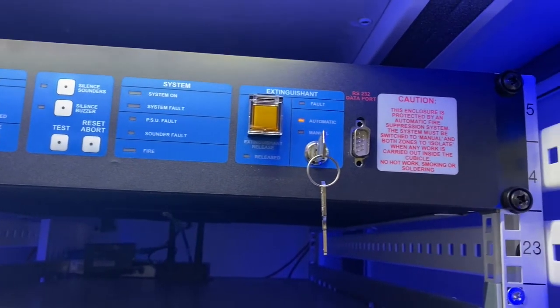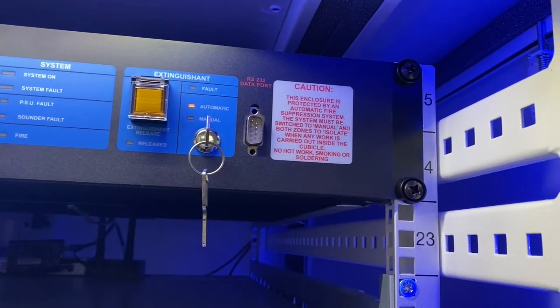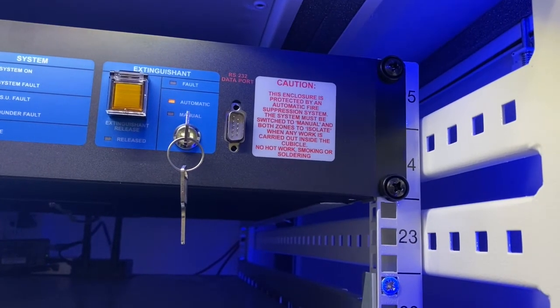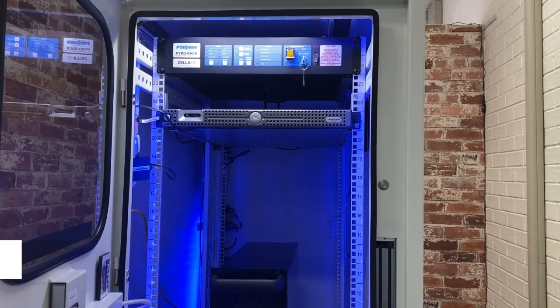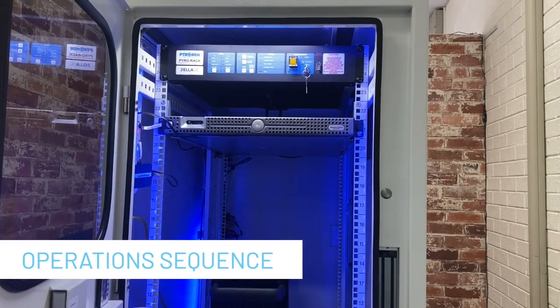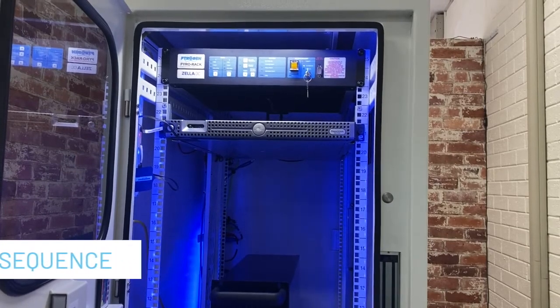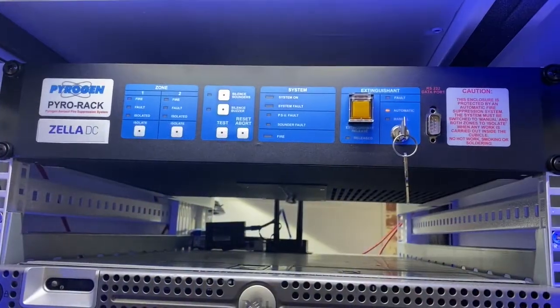When a second smoke detector senses smoke, or when the manual release button is pressed, this sends a confirmed signal that automatically initiates the operation sequence of the fire extinguishing canister. After warning people of an impending discharge, the Pyro-Rack deploys its extinguishing canister that extinguishes the fire within the cabinet, giving customers a last line of defense.